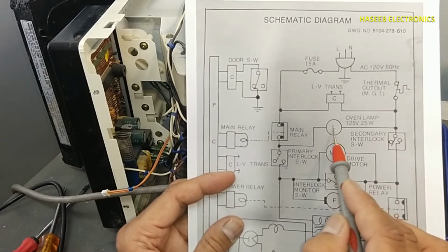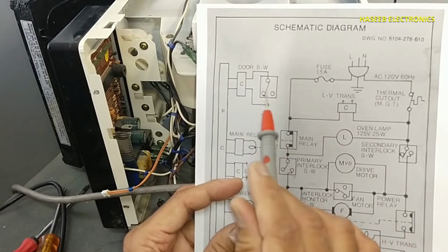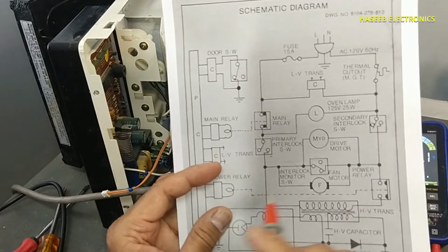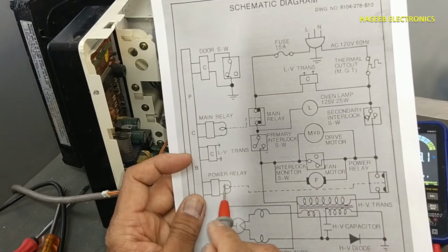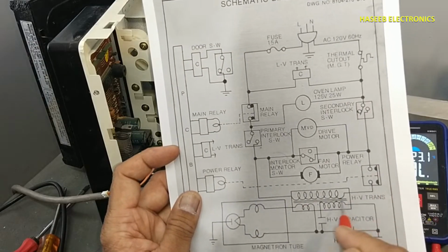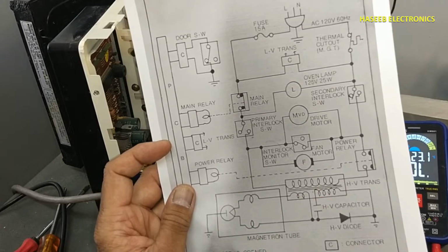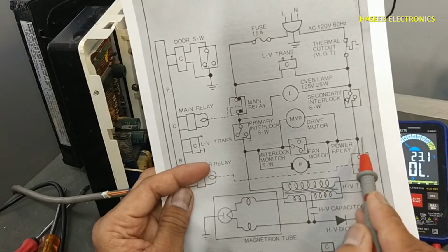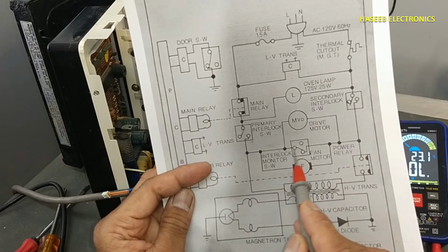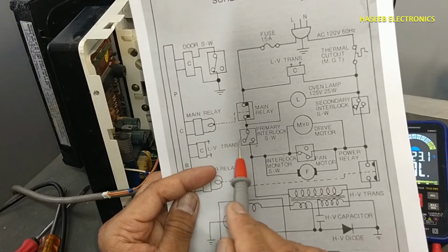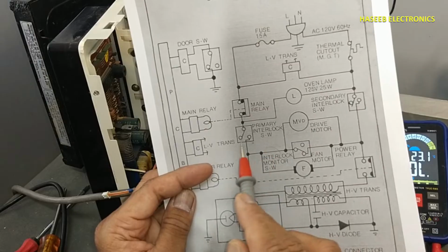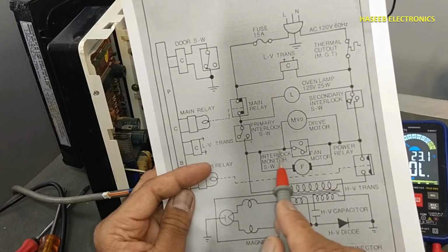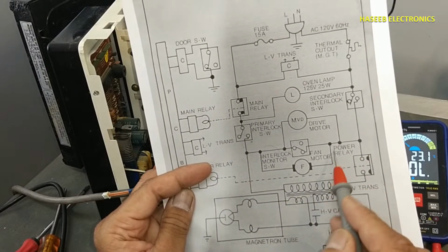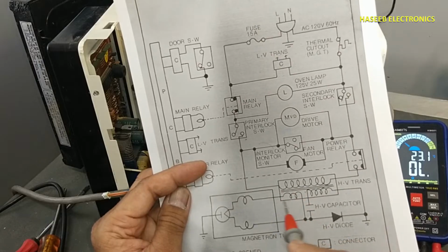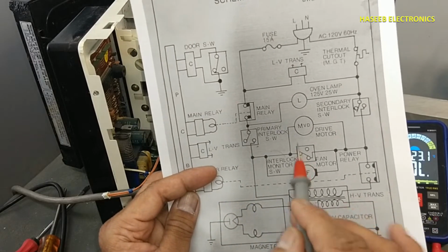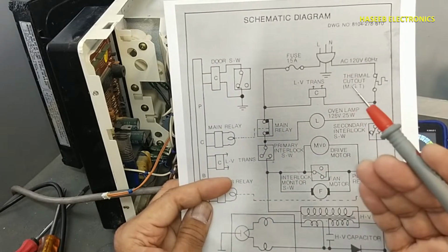This is from the thermal cutout directly to the lamp, and this switch will ensure that the door is opened and will force this relay to remain off. It will not allow the microcontroller to turn on this relay, so that this transformer will not receive voltage. And there is another door interlock monitor, that is this switch, and this switch must be open. If for any reason this switch is short circuited, at that time this switch will make a short circuit and it will not allow the high voltage transformer to turn on because the door is opened. At that time it will blow the fuse or trip the circuit breaker.